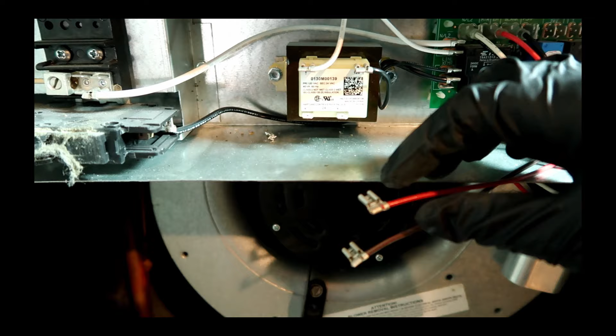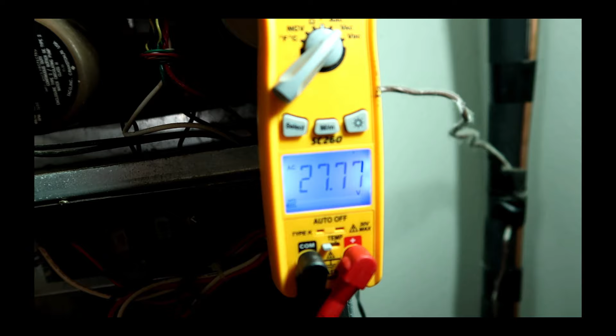I just noticed there's a capacitor in here. I'm used to working on the Goodmans on the older side of this property. They don't have capacitors there. They are the modules, so we should have 120 coming in the high. Yes, we do. We got 120, and we should have 24 to 27 volts coming out of the low voltage here on the bottom. Just noticed the capacitor, so that's probably going to be it. 27 volts, yeah. Transformer is good, so I bet it's this capacitor.